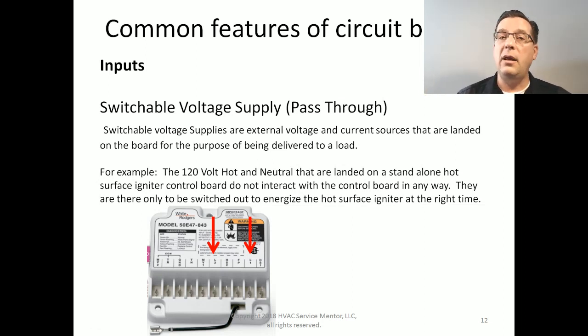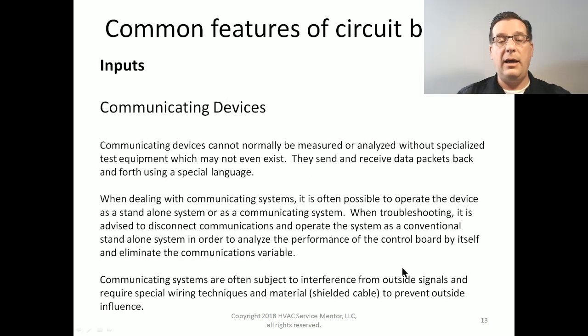Now here's the rub. If for some reason the 120 volts is not present on this control board, the control board is going to operate just fine. It's going to receive 24 volts on demand. It's going to close the switch contacts between the L1 terminal and the HS1 terminal, but nothing's going to happen because the voltage isn't actually there. So we need to identify in a case like that that we have a switchable voltage supply or a pass-through, but it's not there. Therefore, the control board isn't going to be able to energize that load. It has to have the voltage coming in order to send the voltage out. So that's another thing that we need to identify and test for.